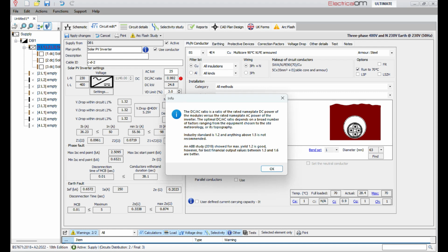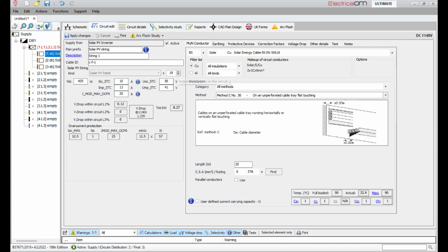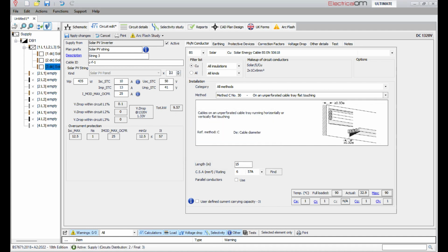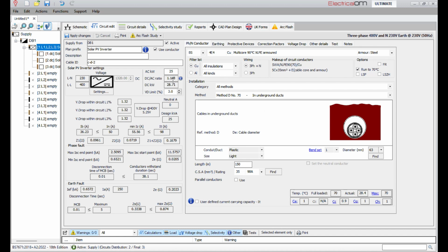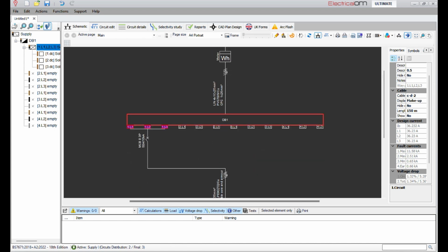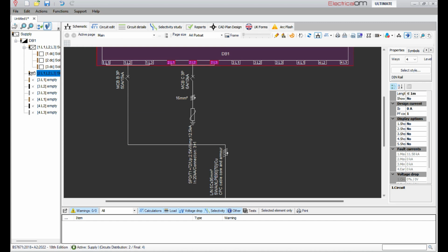And you can see here it's making a suggestion as to your input DC as related to the AC rating of your inverter. Now we can adjust how that appears by changing the number of panels within our strings, or you could change the watts output per panel. I've taken this approach just to quickly illustrate to you how that DC-AC ratio moves to an acceptable value in terms of what OM is telling us, and place the fault away as regards that, or the warning, if you like.